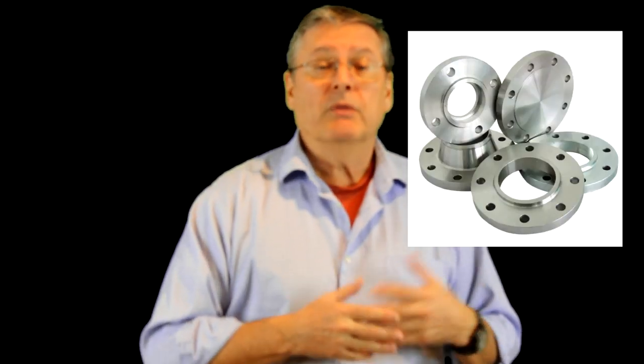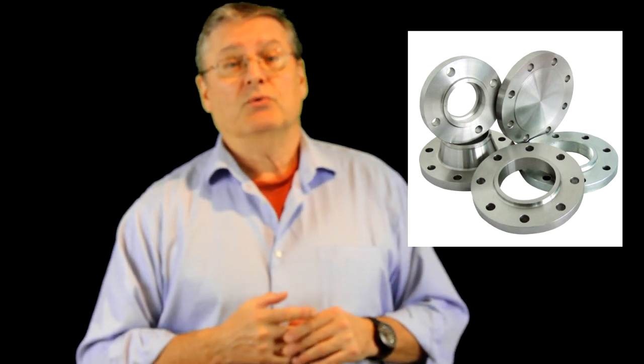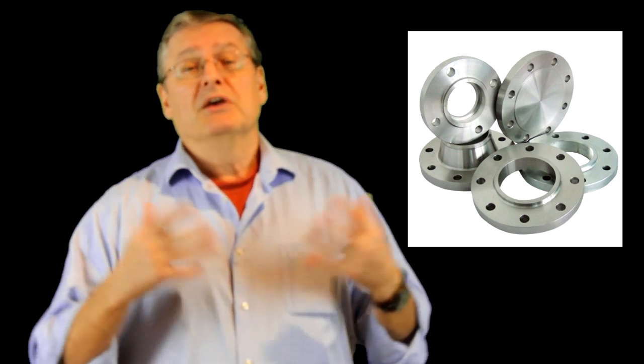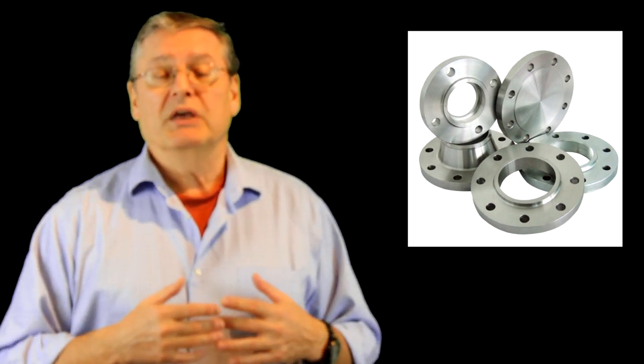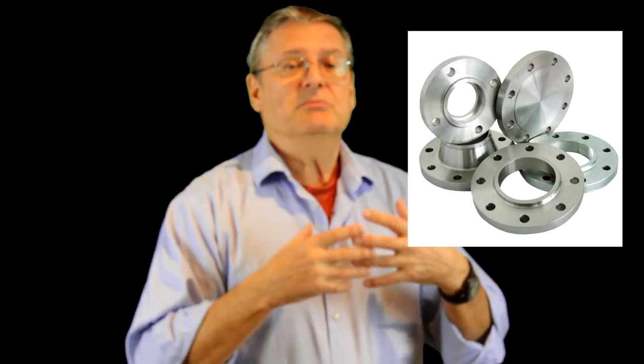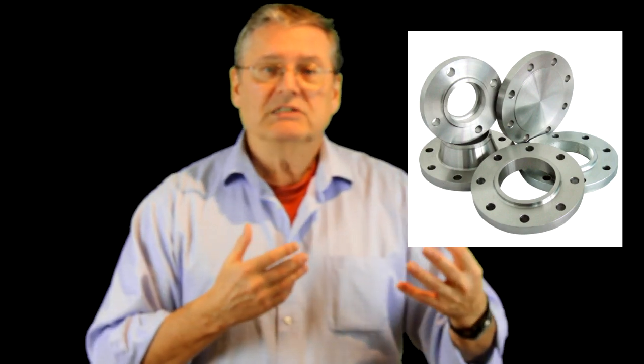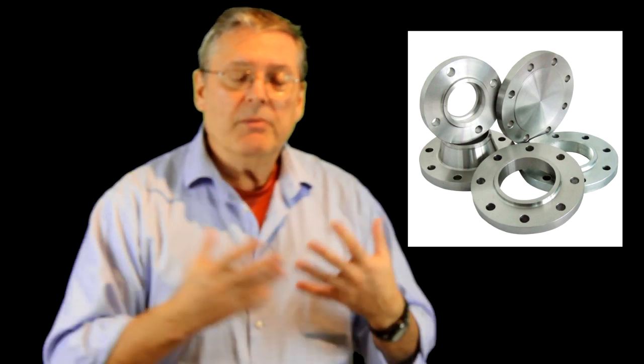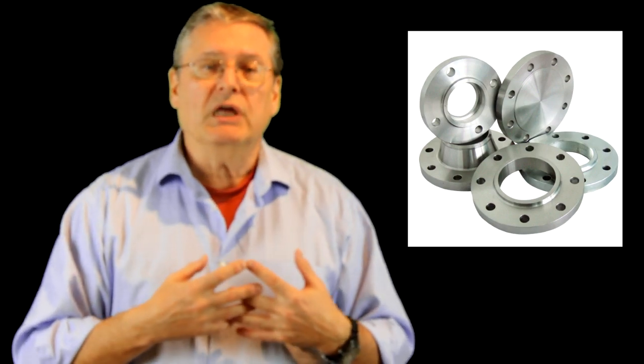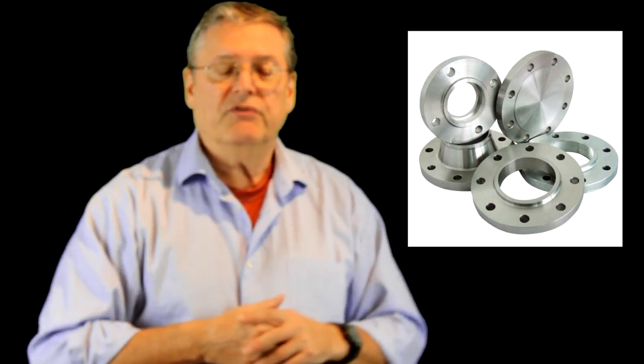I started by trying to show that sometimes there's some confusion about some standards. For example, a class of flange called ANSI 150 pound, if you ask somebody, what does that mean, 150 pounds? A lot of people will say, well, it means it's rated for 150 PSI. Well, unfortunately not, that's not quite the case. It probably was the case once upon a time, but no longer is. This classification system is now more a geometric classification than relating to the actual PSI or pressure that the flange can withstand. So it's related to the bolt circle, thickness of the flange, etc.